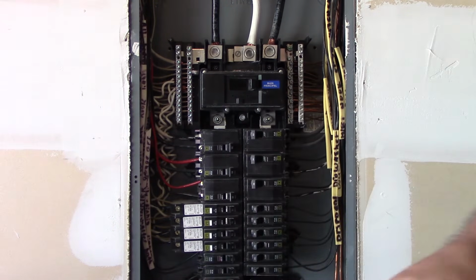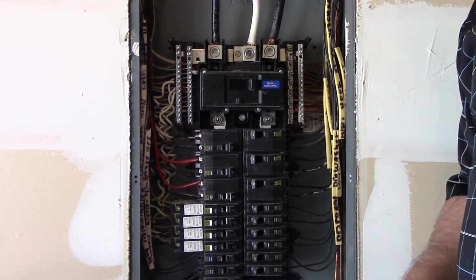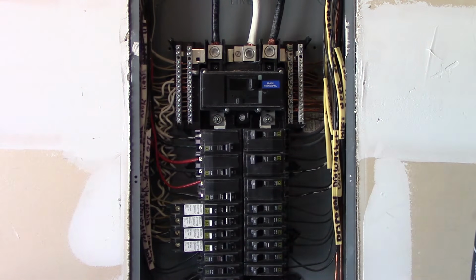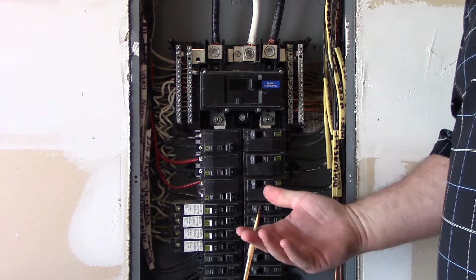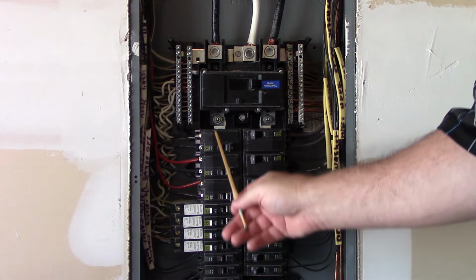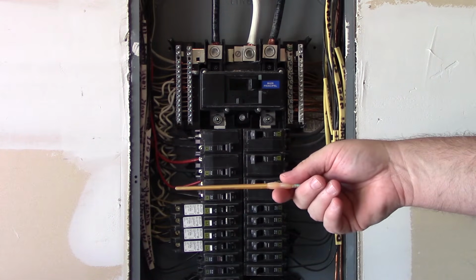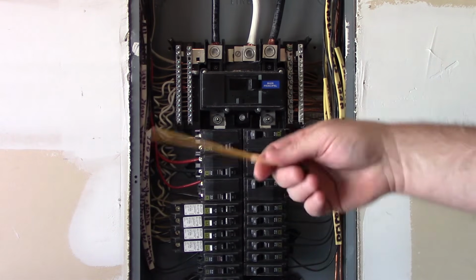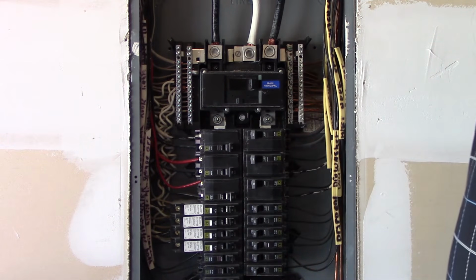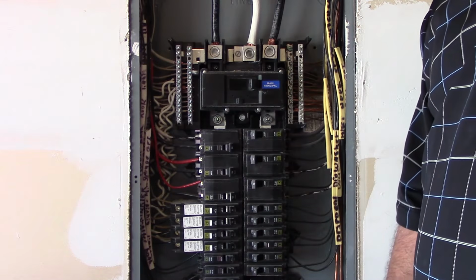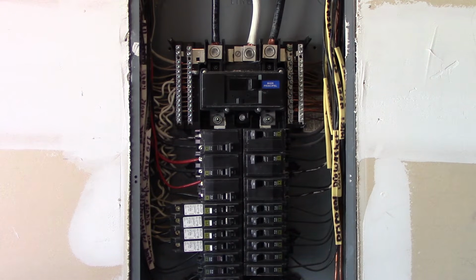79, so about 80. These are elevated about 10 degrees higher for the AFCIs. That's perfectly acceptable. I would expect the same thing if I had a GFCI device in here as well. Okay, so now the reason you don't see any GFCIs in here for like the bathroom receptacle and the garage receptacle is because they actually have GFCI devices in the receptacles that are in those locations, so they don't need to be here. All right, so everything we looked at down there looks okay.